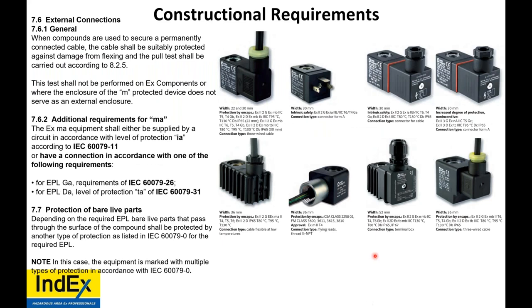So, of all these solenoids, this one's Ex m, this one's Ex m, this one, and this one. The top three on the top row right are not. But as you can see, their construction is very similar. You can have ones where there's no cabling and you have to wire it up, or it comes with the cabling being intrinsic to it. Ones where it is intrinsic, but it could go on a threaded conduit, or a cable gland that you provide goes into it. Or once again, it's integral.